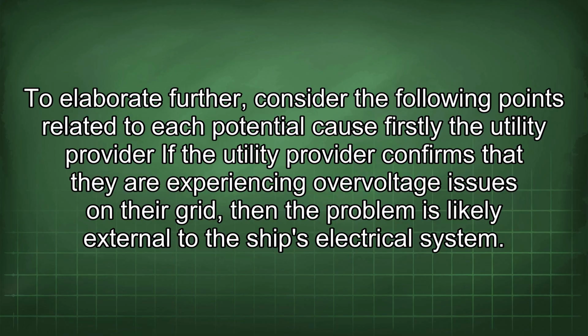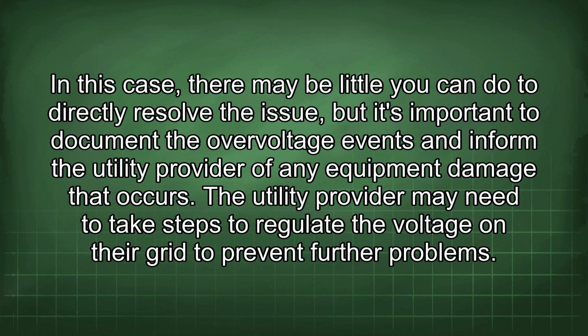Firstly, the utility provider. If the utility provider confirms that they are experiencing overvoltage issues on their grid, then the problem is likely external to the ship's electrical system. In this case, there may be little you can do to directly resolve the issue, but it's important to document the overvoltage events and inform the utility provider of any equipment damage that occurs. The utility provider may need to take steps to regulate the voltage on their grid to prevent further problems.